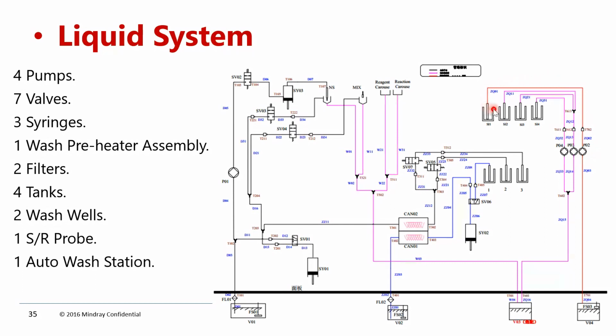Why? Because we are going to clean this cuvette, right? There shouldn't be any water bubble or molecule here. So to clean it effectively, we are using one wiper, a Teflon wiper, and we are applying the high vacuum from pump 02, so that it will wash the cuvette effectively. That is one reason why there won't be much liquid in this line, and you are observing a lot of deposit, dust like this, in this tubing, the red color tubing here. Okay, red line, waste line.